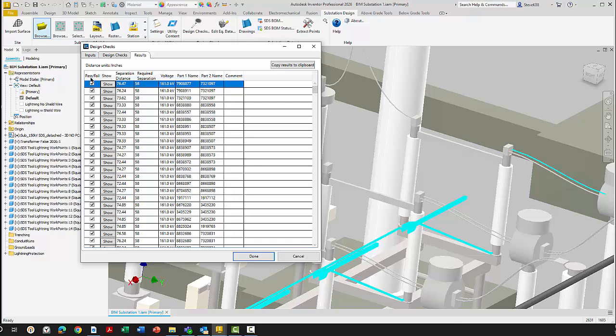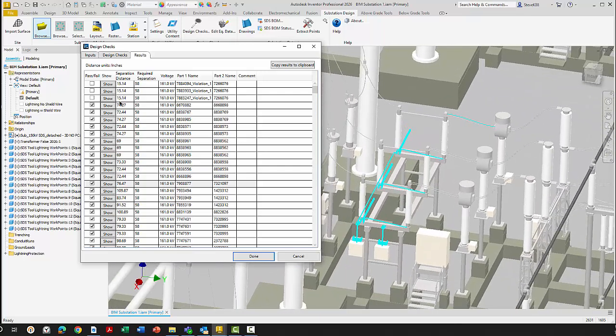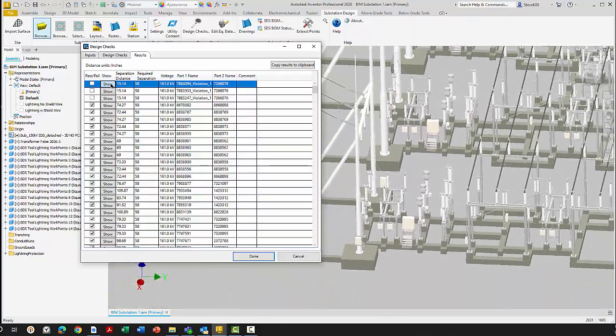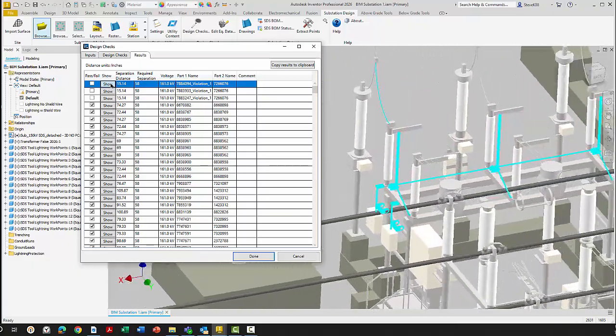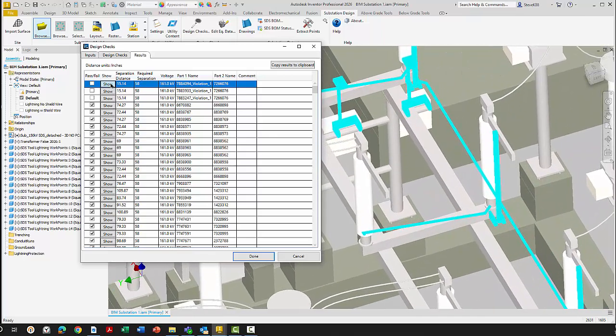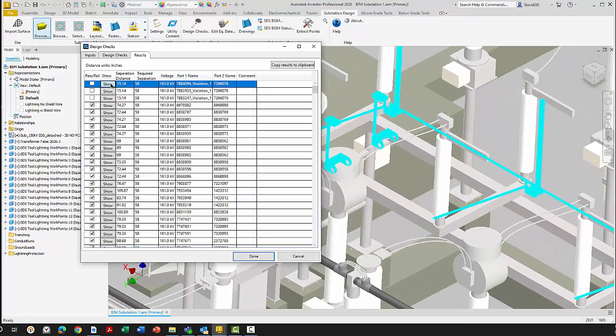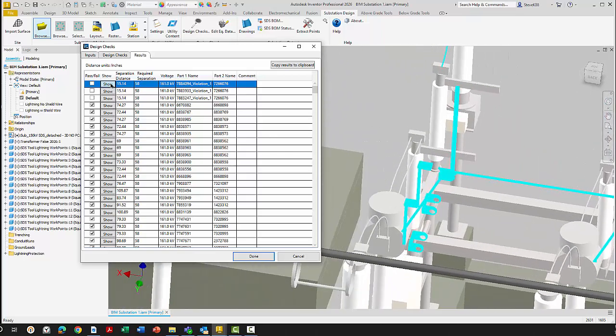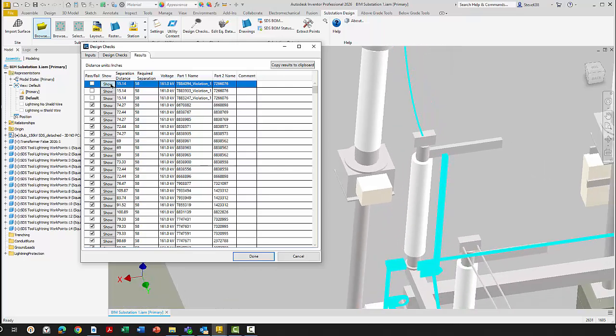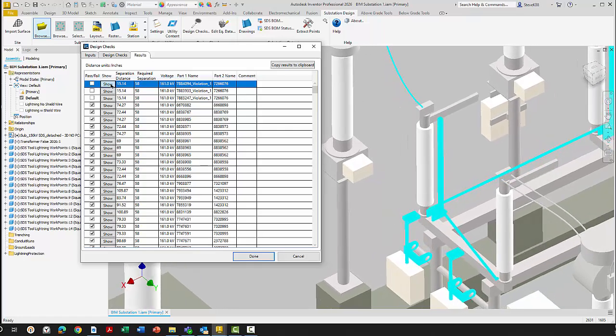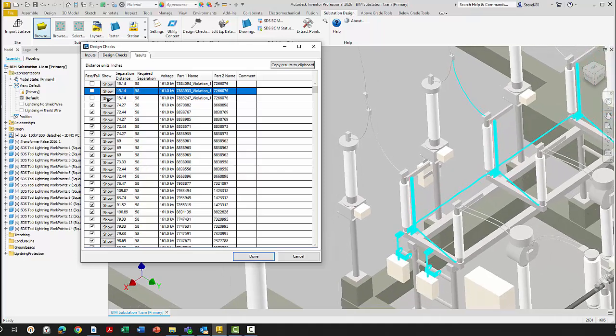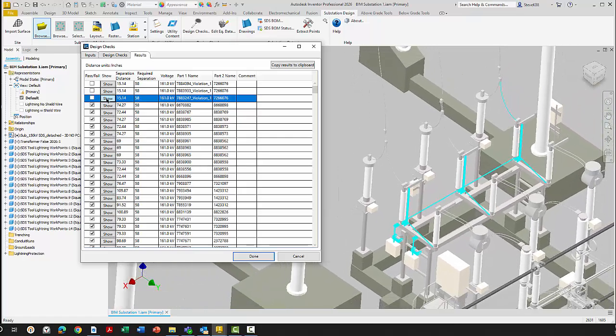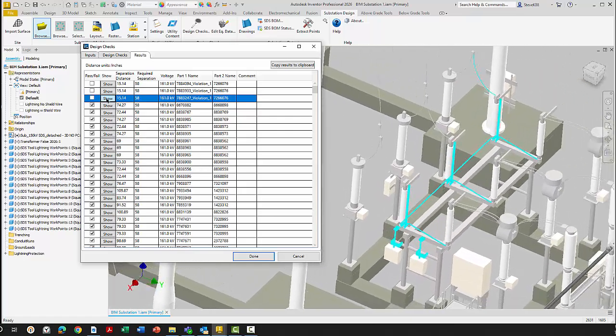If we sort on the pass fail, you can see it's failed in several spots. So maybe we should look at these spots and see what it is. We'll see if it's a true fail. Sometimes it's a false fail because of the way something was modeled. In this case, it's showing the mechanical switch is in violation with the wire here. The wire is too close to that switch. But that switch wouldn't be energized in this case because the switch is open. Same idea - all three phases failed on that. So that could very well be a false fail because it is not energized.